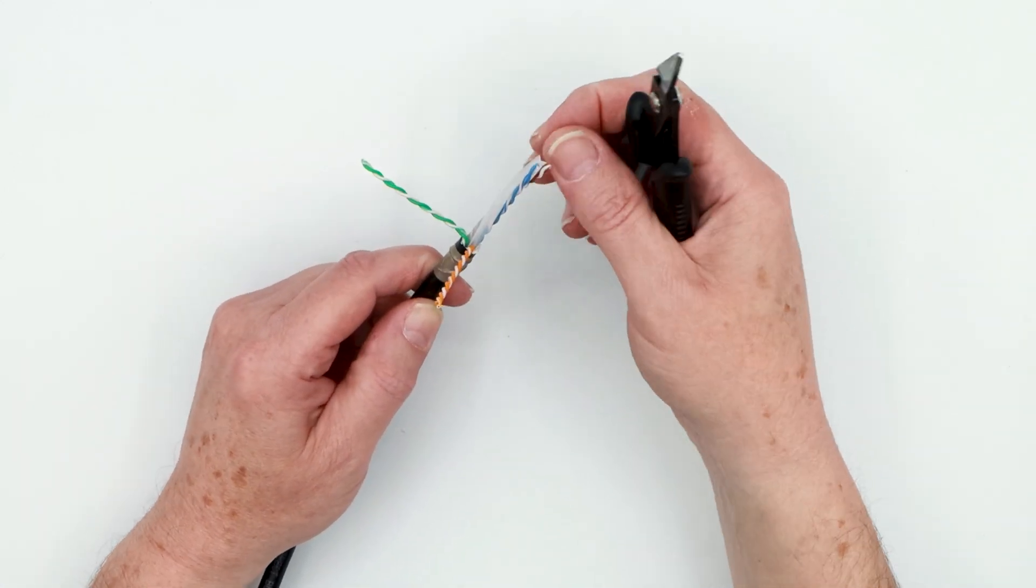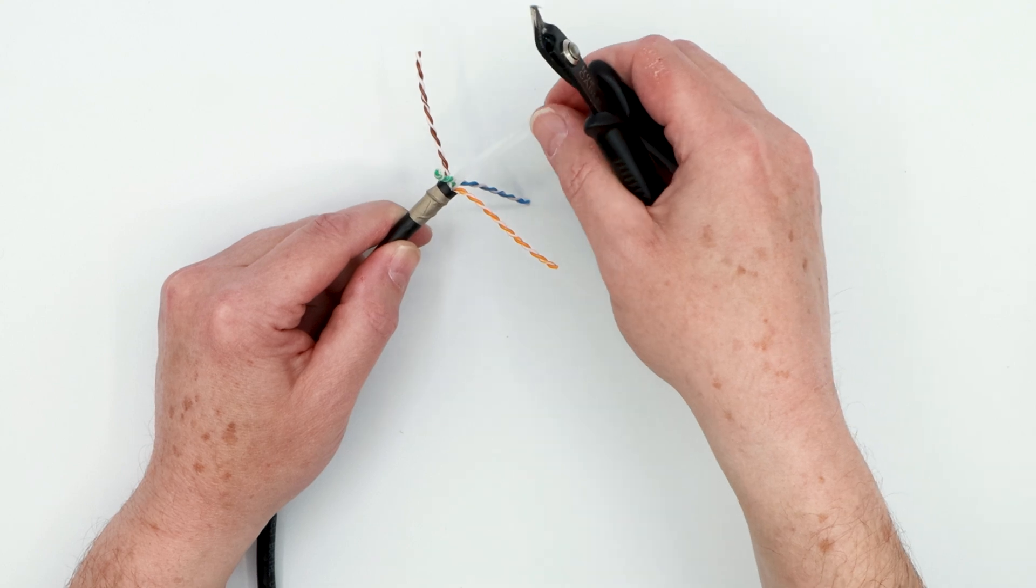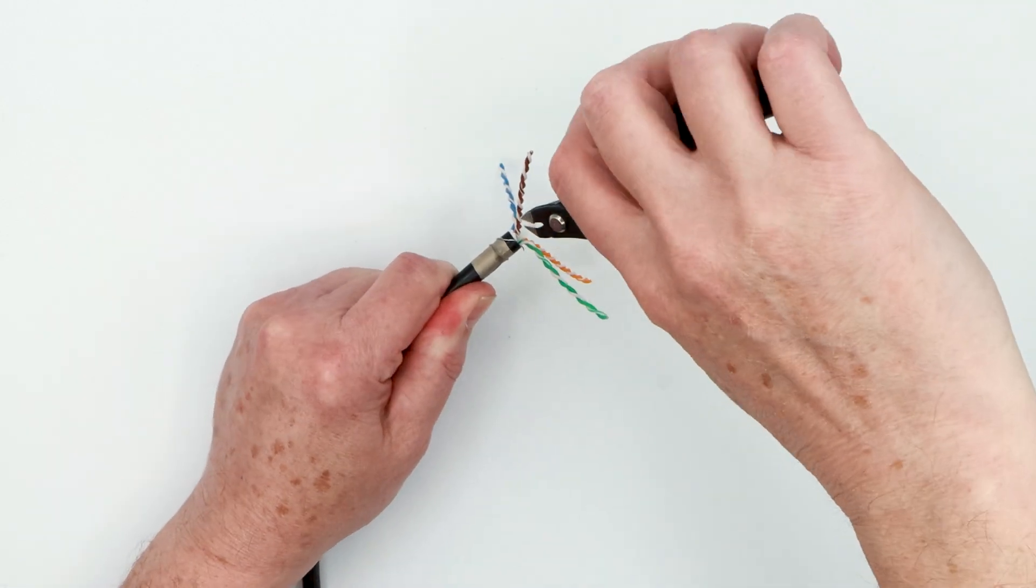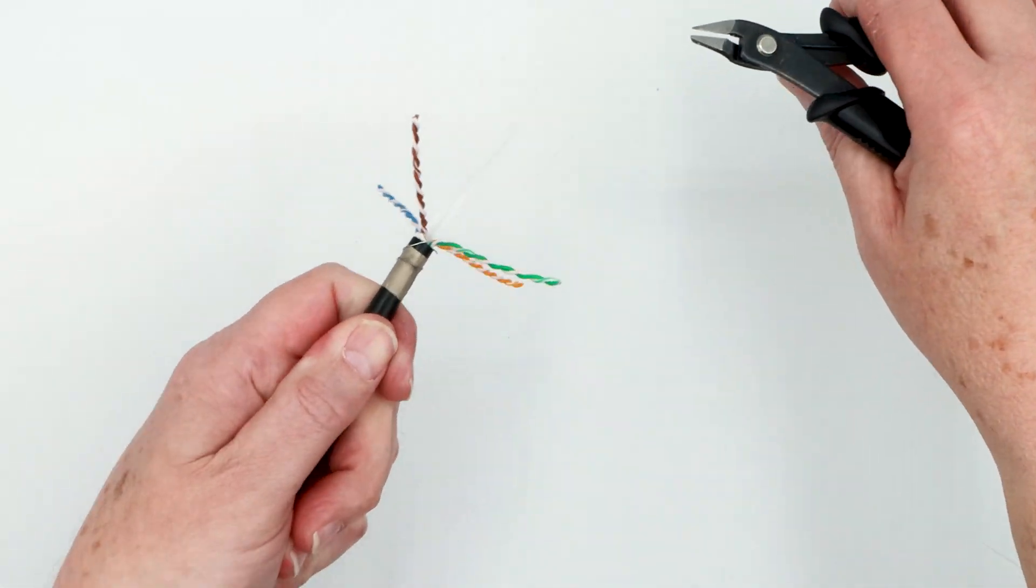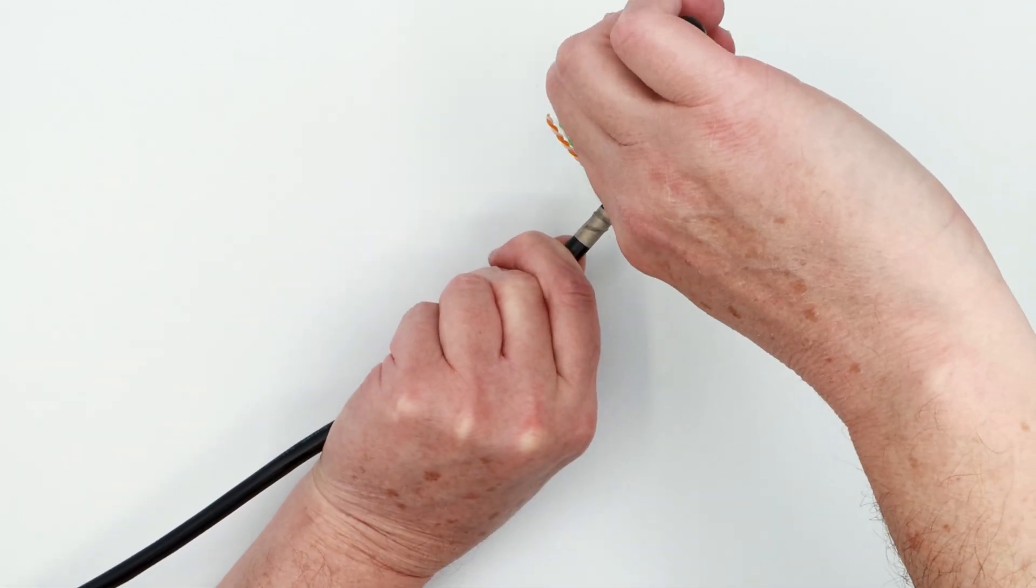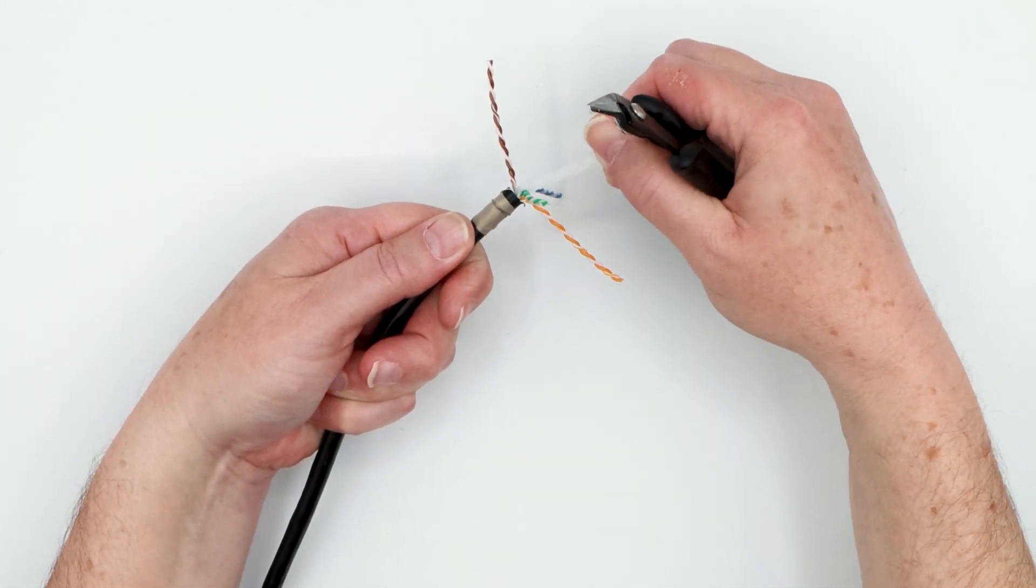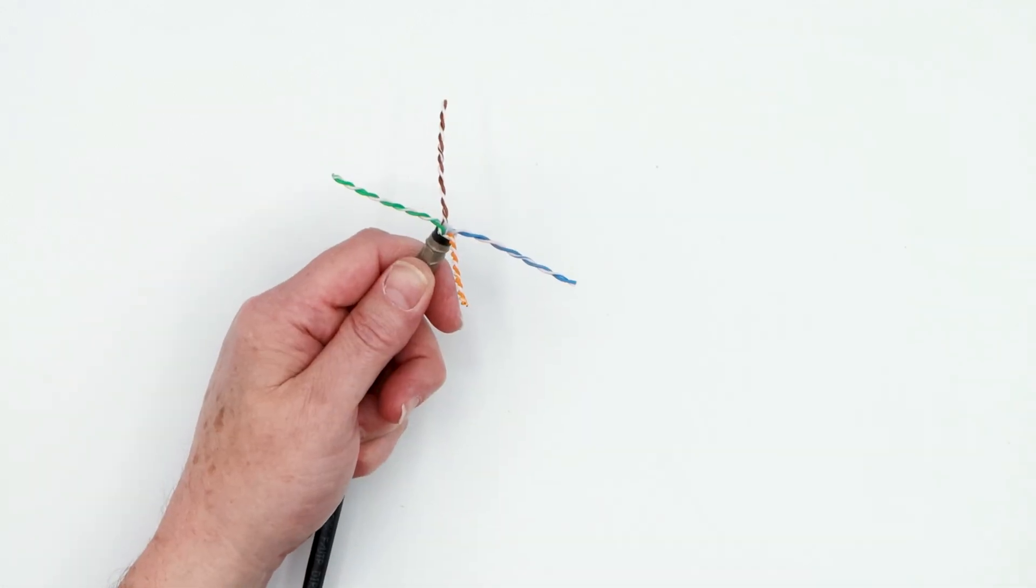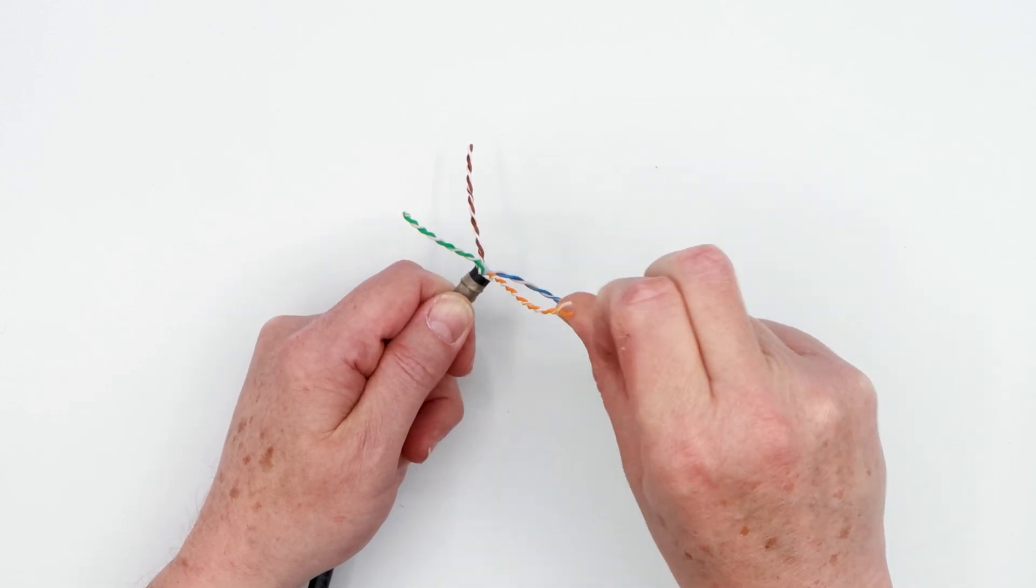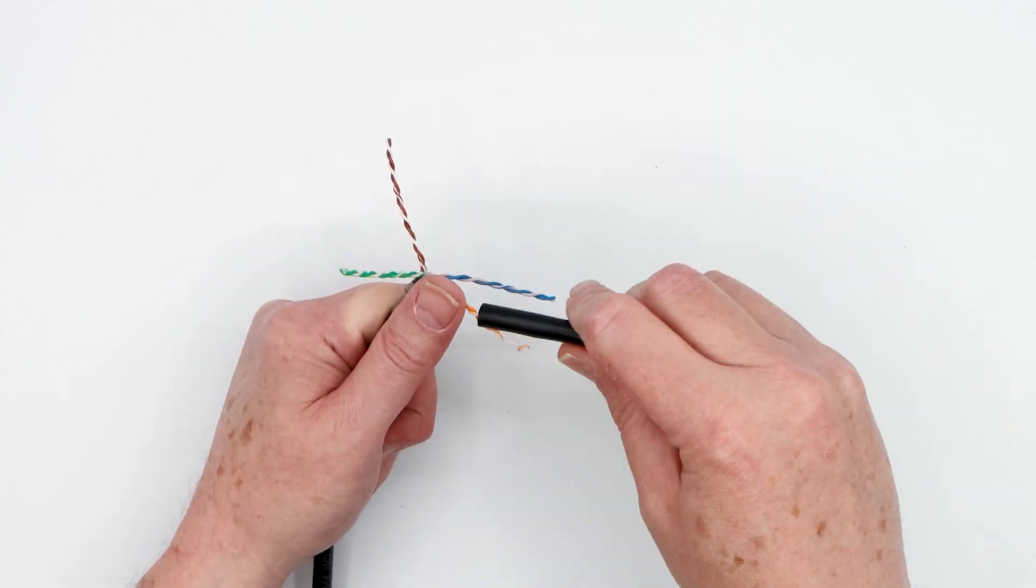And then the next is to go ahead and separate these conductor pairs into a star pattern. The spline has four wings and you want to at a downward angle cut each wing as close to the cable jacket as reasonable as possible without accidentally nicking a conductor in the process. So make four snips and then simply twist the spline and it comes right off. The next step is you want to untwist your conductor pairs. So we've got four pairs with eight wires. So we're just going to go ahead and untwist down to the jacket on all four pairs.